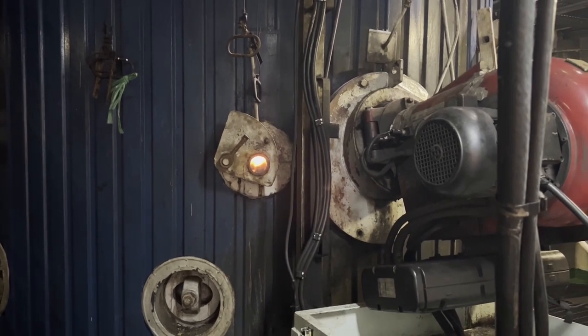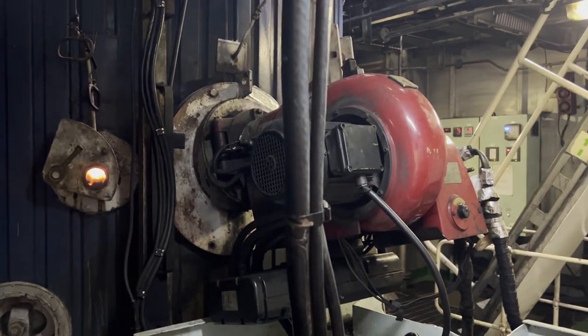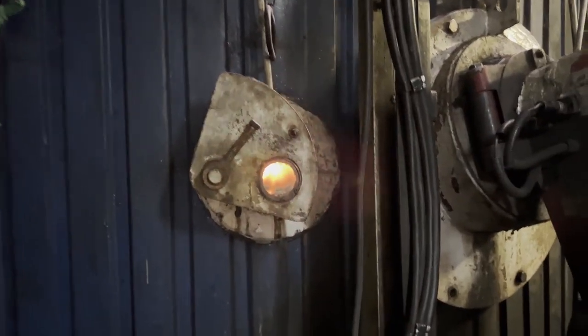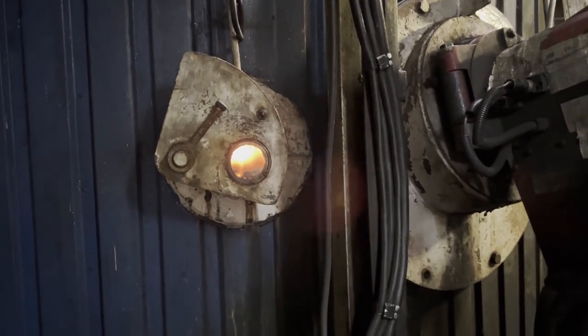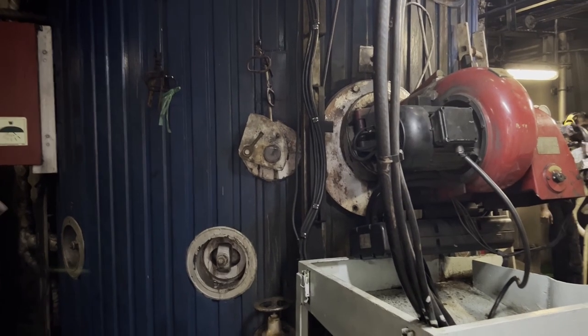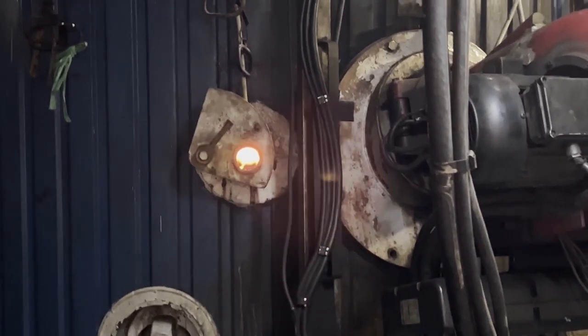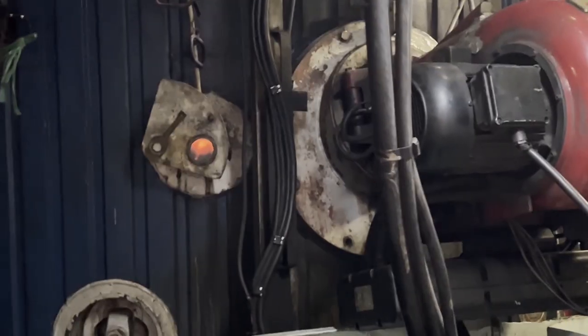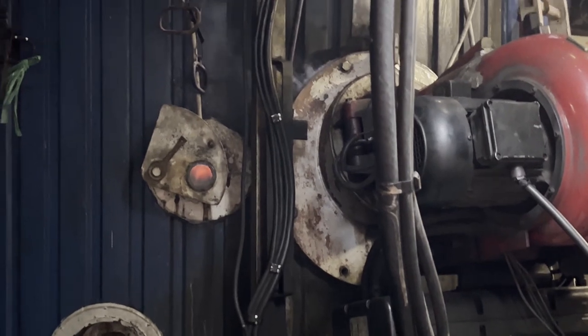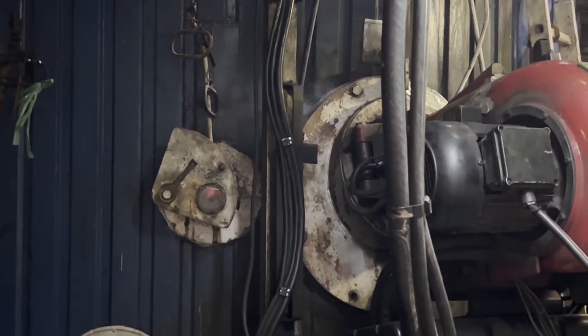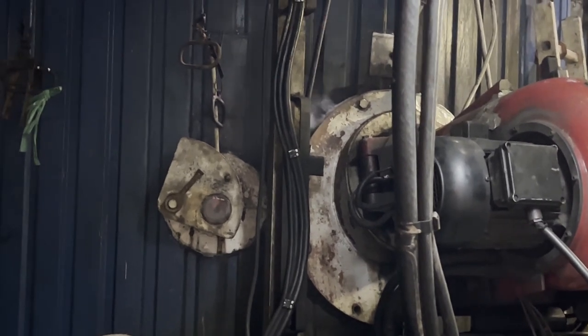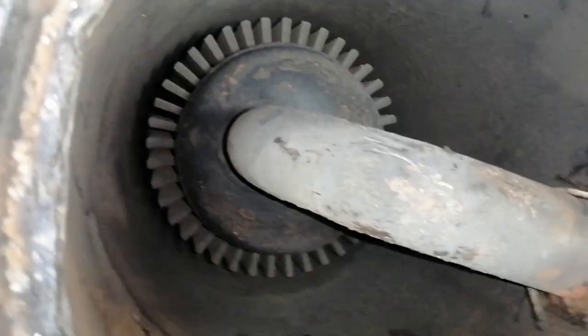This is the indication of backfire because the amount of fuel which is burnt, that exhaust gas should go out. Because of the non-availability of space, both fin tubes are fully choked so the gas couldn't go out. Instead there will be a pressure buildup inside the chamber and the exhaust gas takes the easiest path through the flange outlet. If the boiler continues this way it may cause a backfire which may lead to a major fire.